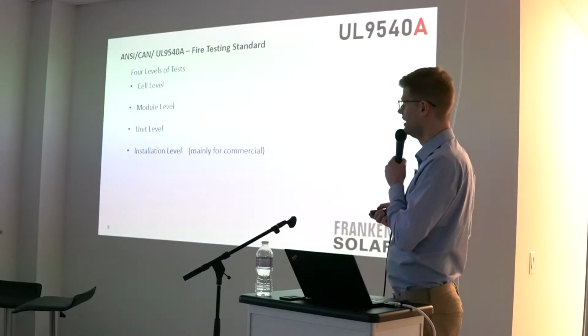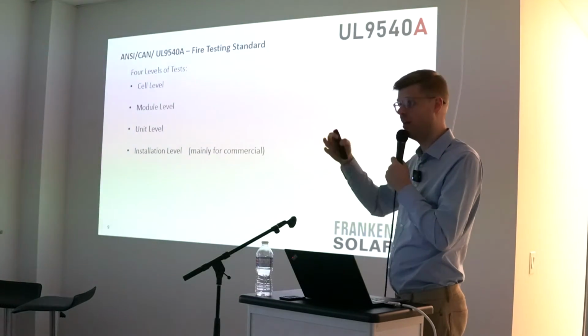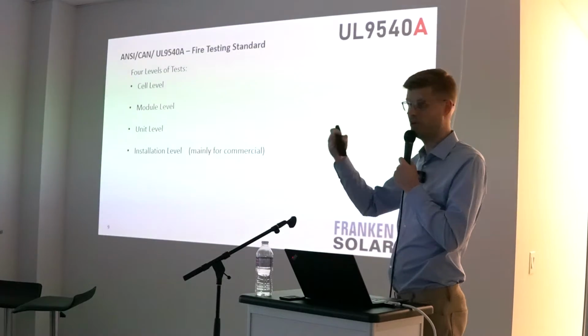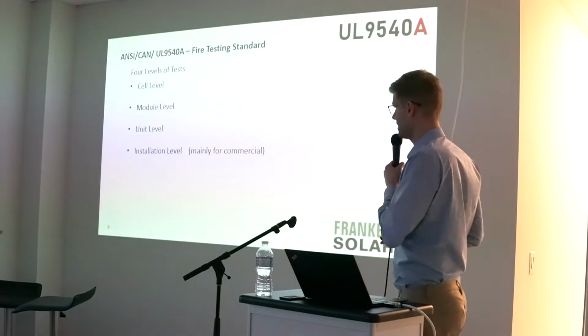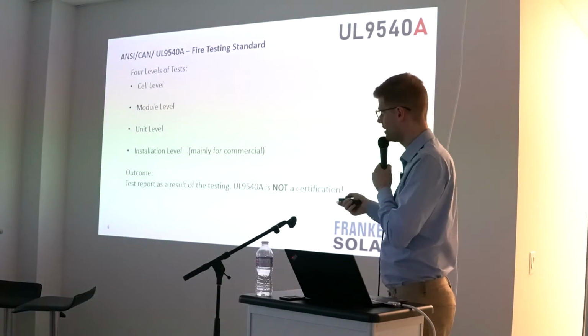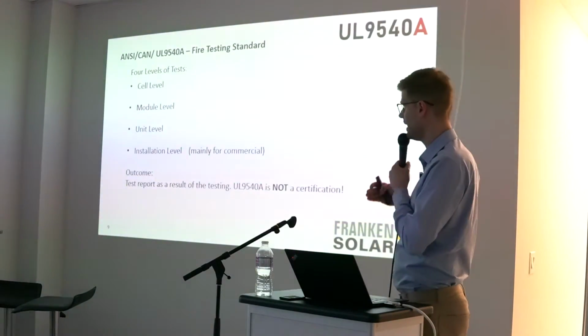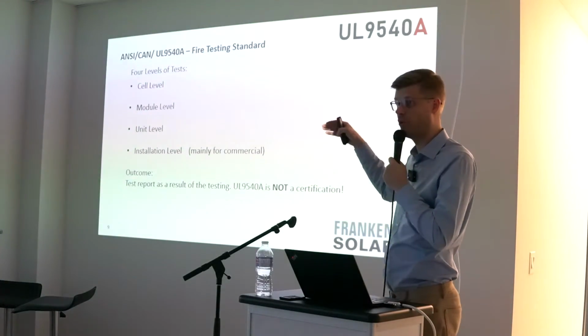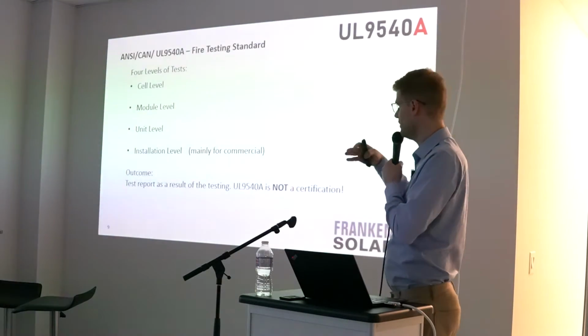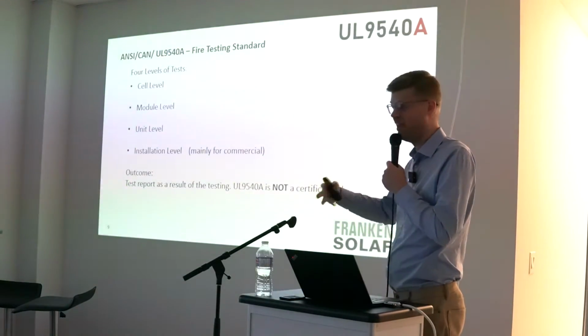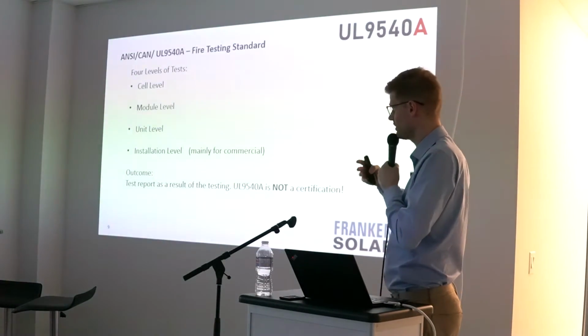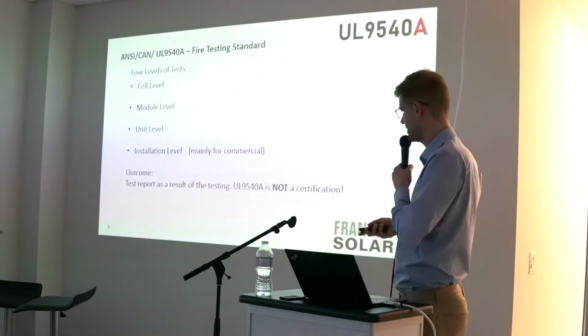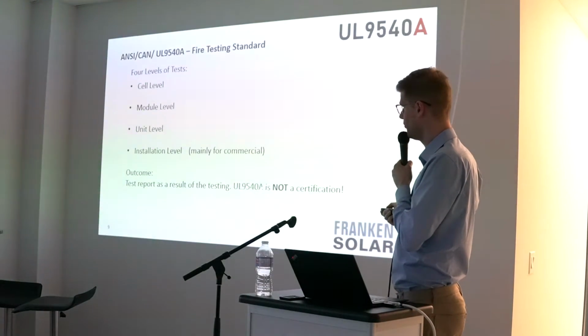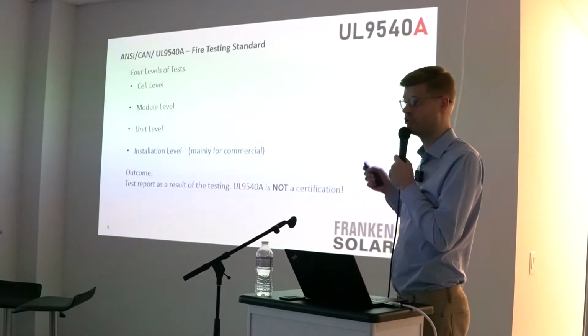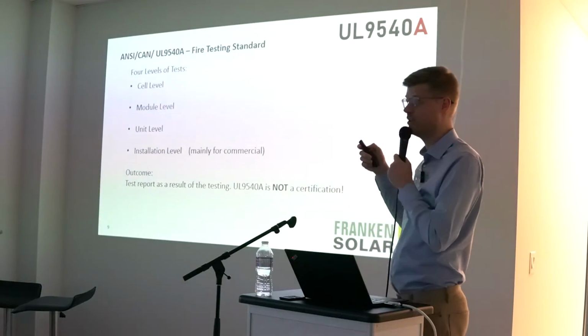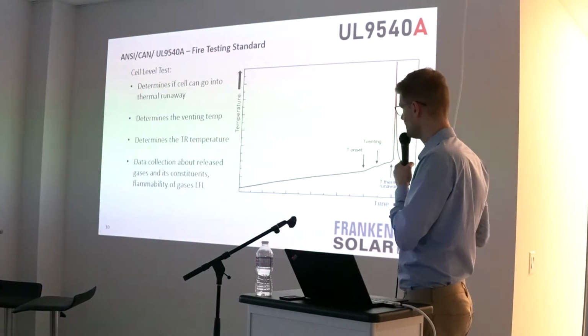Certification is the wrong word; it's testing to an installation level that includes all the other safety mechanisms, like a fire suppression system, smoke detection, or a sprinkler system, for example. The outcome will be a test report that shows exactly how that cell, module, or unit reacts to the test, and if there is any fire, flame, or flammable gases, or accumulation of gases, all of that will be tested. But the UL9540A is not a certification on its own. It's just a testing method to support the UL9540 system testing or certification.